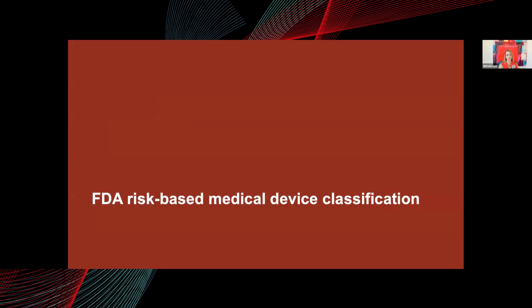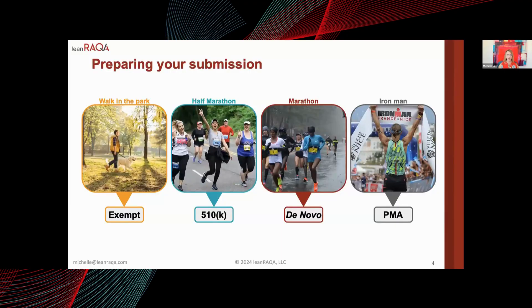One of the first unique things about the US compared to the MDR methodology is that the MDR uses a rule-based approach, while the FDA uses a risk-based approach involving different types of submissions based on the risk structure of the product. For super low-risk devices, the pathway to market in the US might be a walk in the park — it could be 510k exempt and even GMP exempt.